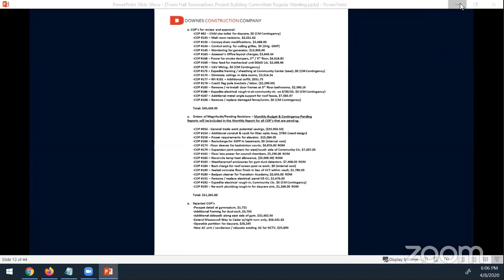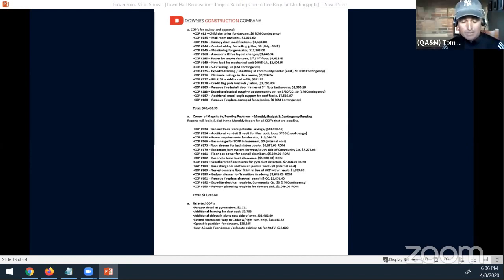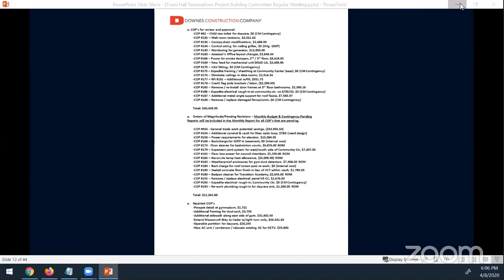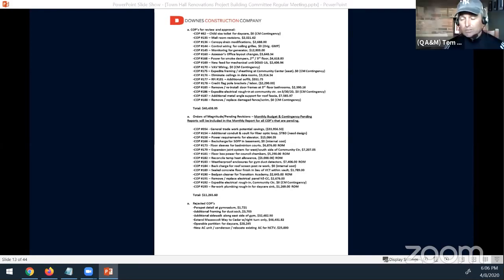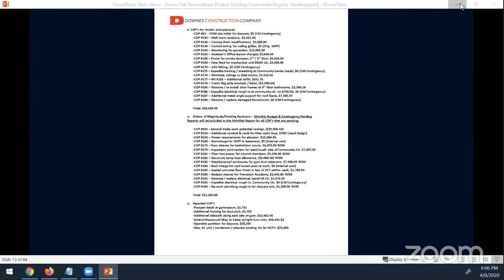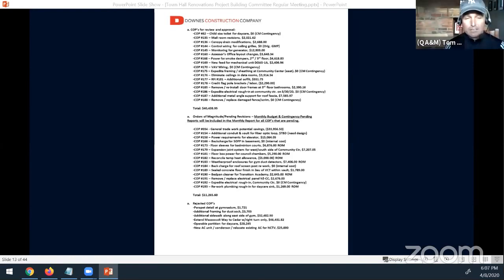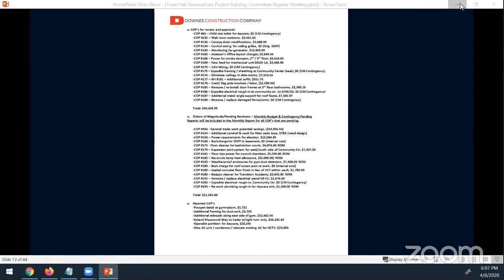Not every single microwave will be running at the same time, that's just an example. So to determine the actual load on the generator, the realistic, the median load on the generator, you can't determine that until we do the 4-day testing to get a feel for what the general loading is, to establish the mean.